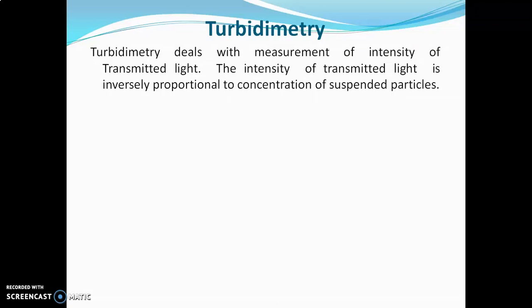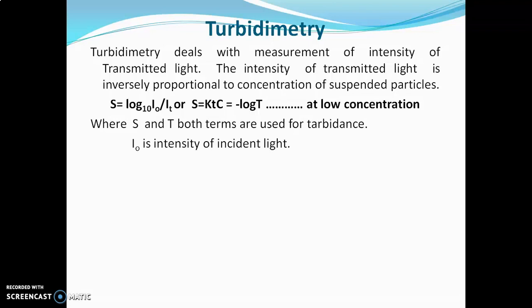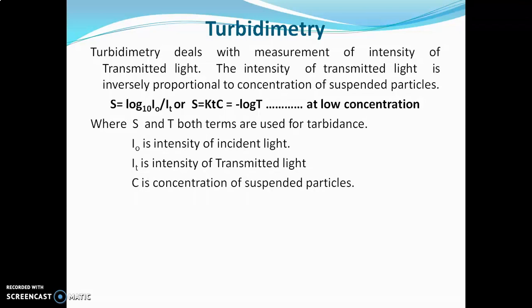Turbidimetry deals with measurement of the intensity of transmitted light. The intensity of transmitted light is inversely proportional to the concentration of suspended particles. At low concentration, this technique follows Beer-Lambert's law, and the equation is: S = log₁₀(I₀/Iₜ), or S = KTC = −log T. This equation is for low concentration solutions, where S and T are both terms used for turbidity. I₀ is the intensity of incident light, Iₜ is the intensity of transmitted light, C is the concentration of suspended particles, and K is the constant.